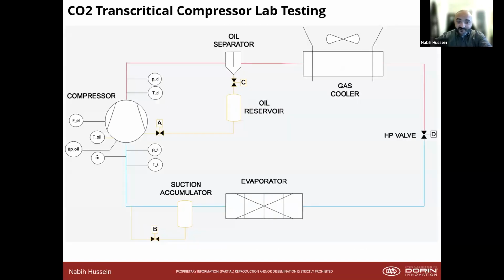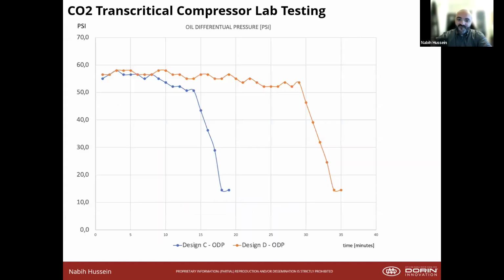So what we did is we turned off all oil returning to the compressor, so it can only run as long as possible without oil returning to it. Once the oil carryover has reached a point where it trips its oil pressure sensor to cut off the compressor to protect itself, this is how we tell if there is low oil carryover. So we did see an improvement with the internal partition. It did give it an extra maybe 15 minutes of runtime, and that's 15 minutes longer in the field where someone can resolve an issue.